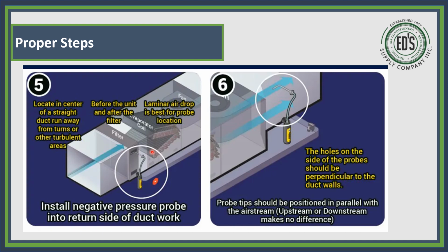Just like on the furnace, you want to test it in the blower motor compartment as it has already passed through the filter. If you're testing it on the air side of the filter, not the blower side of the filter, you're not getting any resistance reading of what that motor is under. And I want to know what that motor is under, because that restriction is going to determine how many CFMs that unit or furnace is putting out.